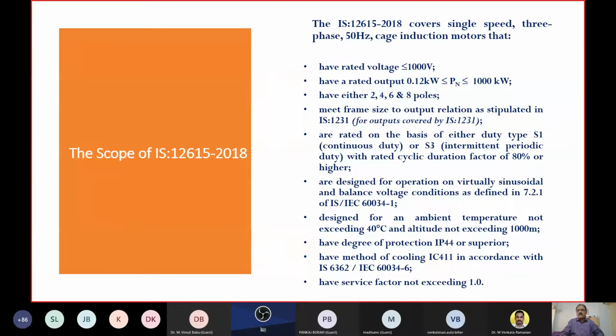These motors are rated on the basis of either duty S1, which is continuous duty, or S3, intermittent periodic duty, with a rated cyclic duration factor of 80% or higher, which in other words simply says it is S1. So other than S1 duty motors, the standard is not applicable. For S2, S4 or S5 or others, the standard is not applicable. These are again designed for operation in virtually sinusoidal and balanced voltage conditions. Although the nameplates of motors will carry plus or minus 10% for voltage, plus or minus 5% for frequency, and plus or minus 10% for the absolute value of these two put together, the standard clearly stipulates that the efficiency is available only when the motor operates with balanced loads and without fluctuations.